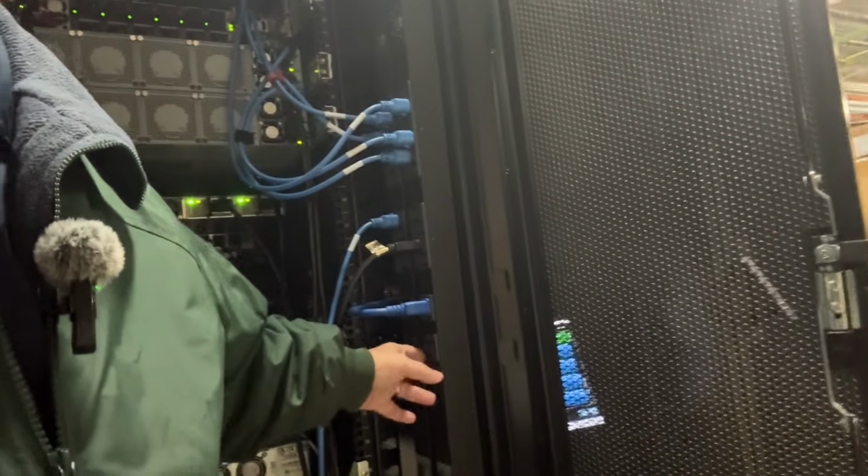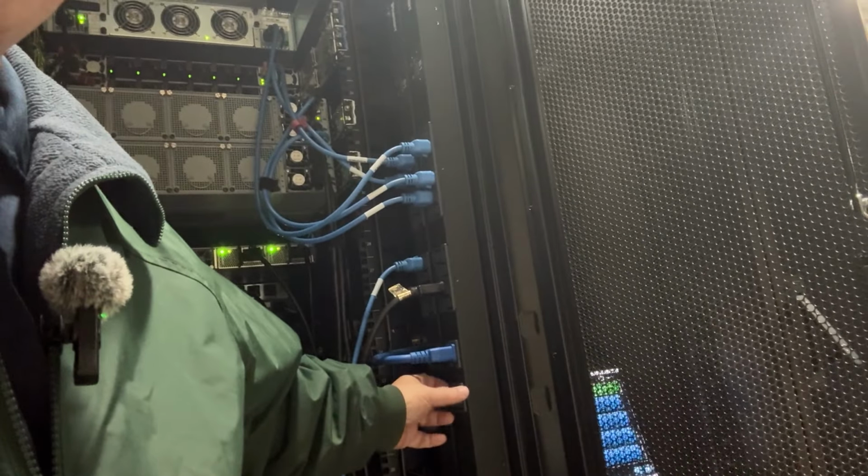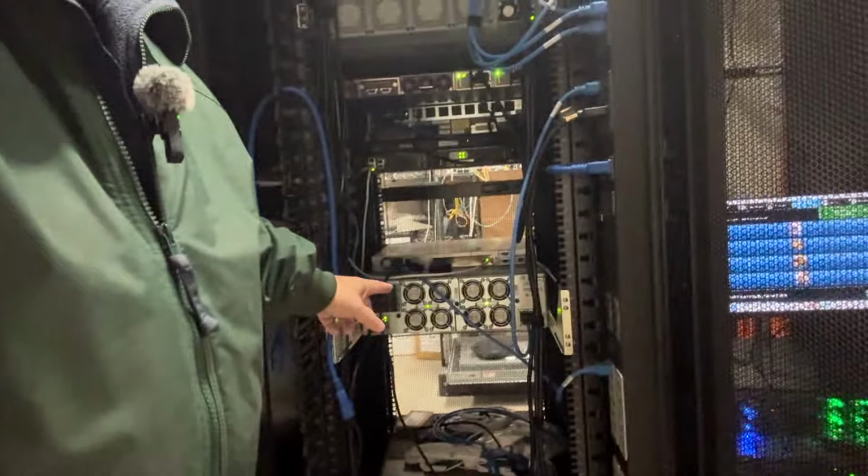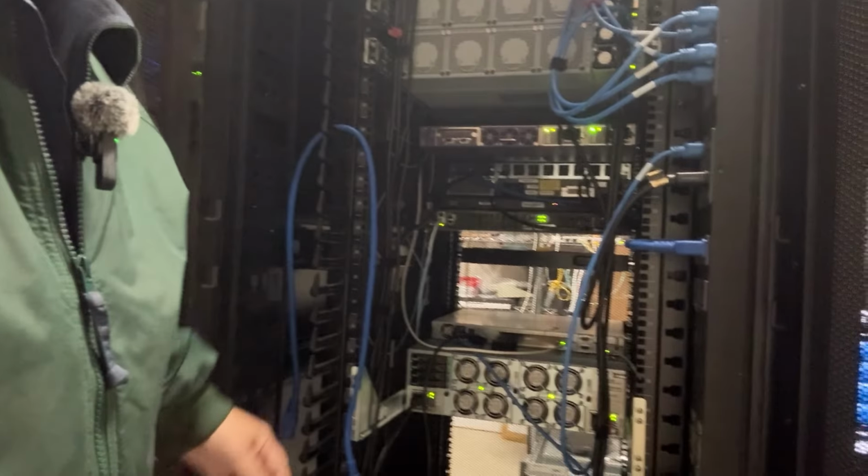While this does go to emergency power, the generator will come on. When we're making that cutover from utility power to generator power, this drops for a few seconds, just long enough for that to drop. So that's why I put these UPSs in down here.